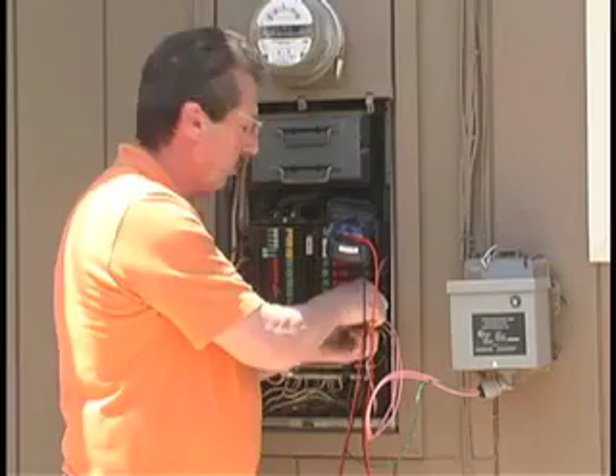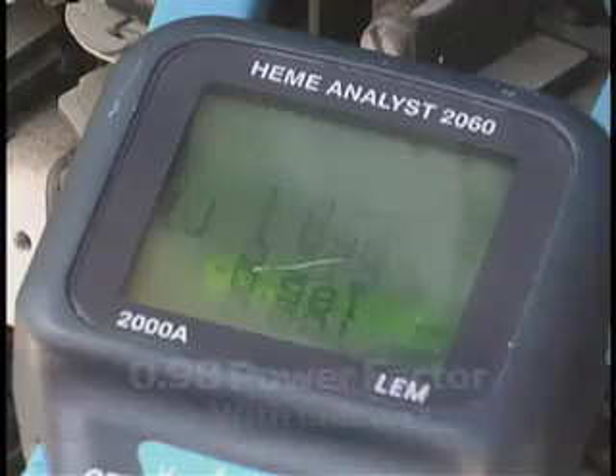As far as the power factor, we change it to the power factor setting and we find that the power factor with the unit off was extremely poor, 0.05. With the unit on, it increases to 0.98. A significant increase, probably the most dramatic increase I've seen on power factor improvement.